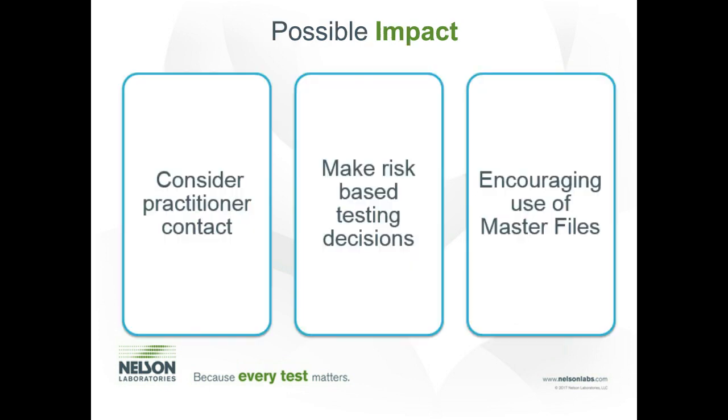Some of the possible impacts: the practitioner contact. In the new guidance document, the FDA has put in a concern for the practitioner or the user of the device. This only applies if that practitioner does not have appropriate clothing to protect them from the device. If they're gloved and masked and everything like that, then the risk is really low. But if they're handling your device without those protecting layers, we need to evaluate that too.